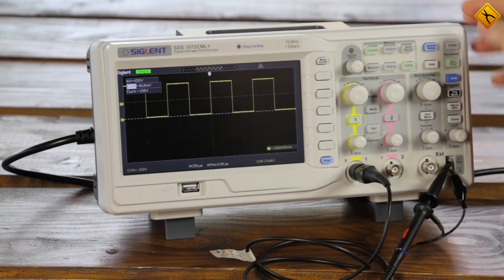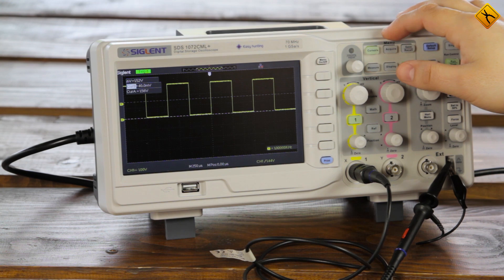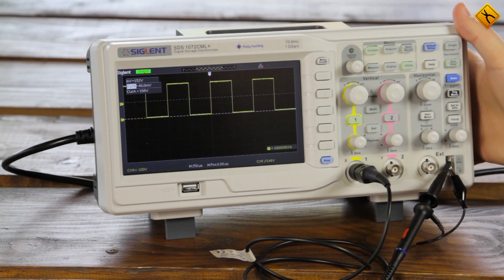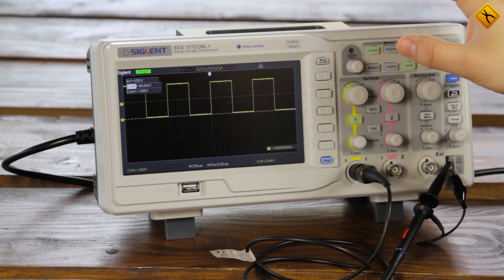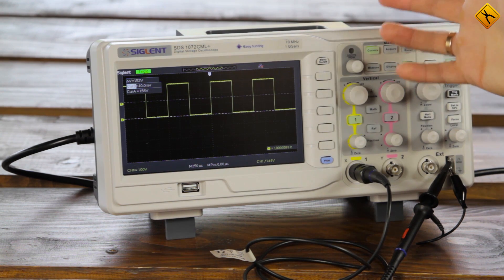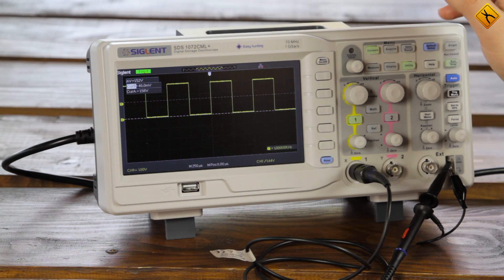Hello! In today's video I will talk about how to calibrate an oscilloscope and why it is necessary. An oscilloscope is a very precise and sensitive piece of equipment. Even the slightest changes in the parameters of the surrounding environment can affect it — temperature, pressure, humidity, and so on. Therefore, when abrupt changes in these parameters occur, the parameters of the oscilloscope have to be adjusted as well. This process is called calibrating.